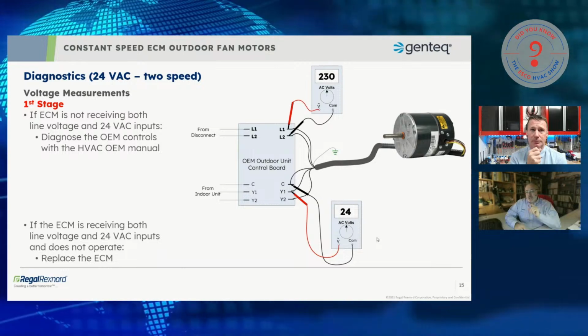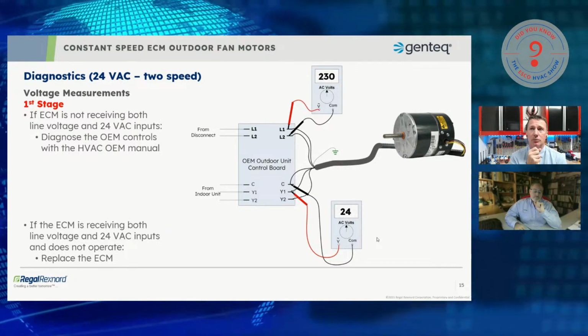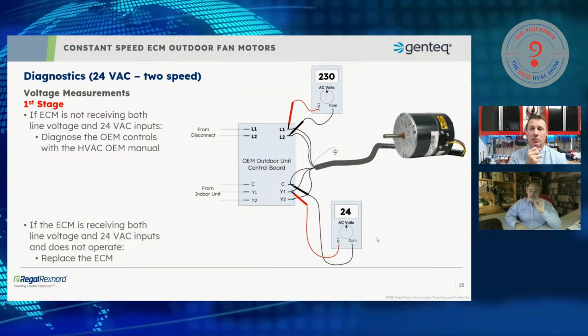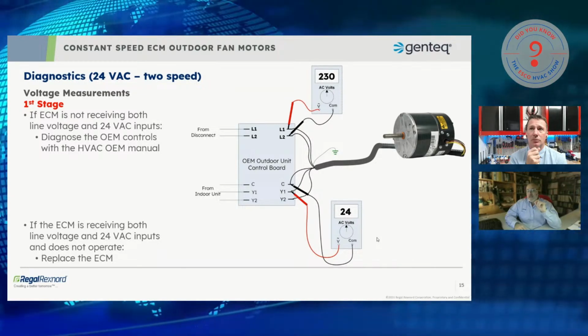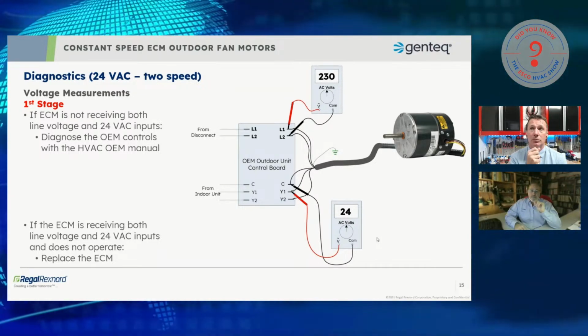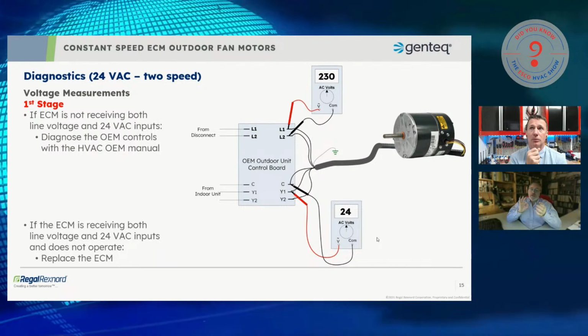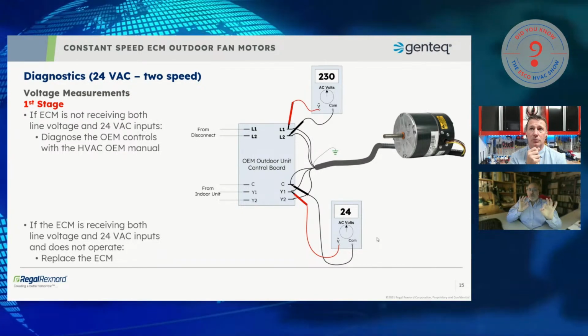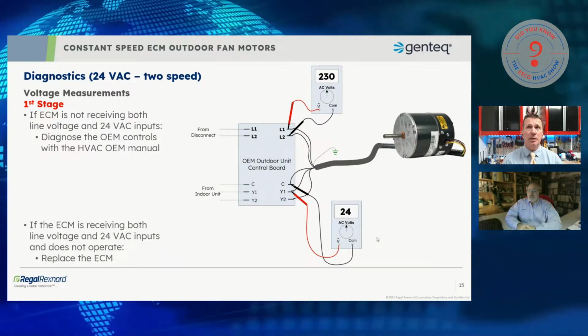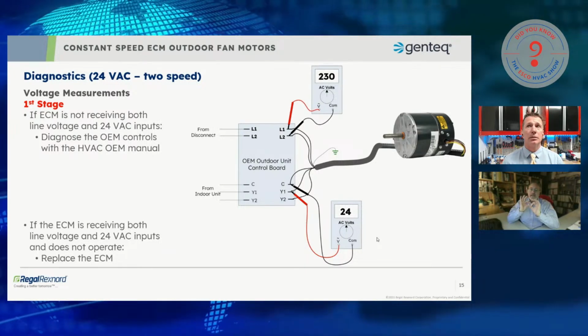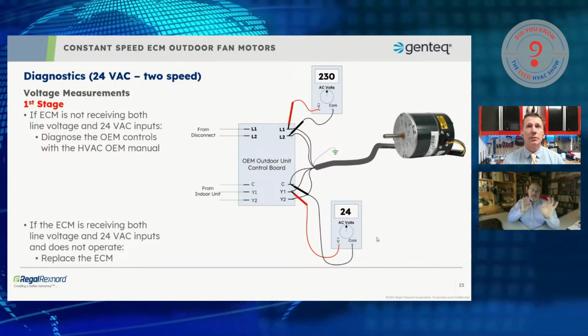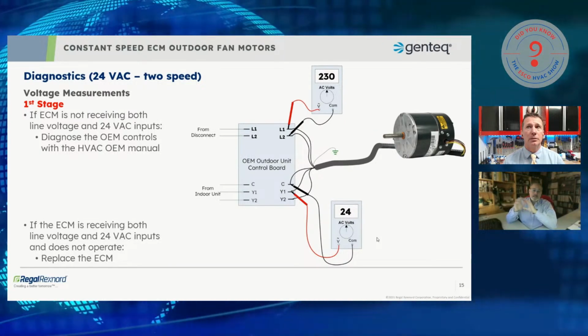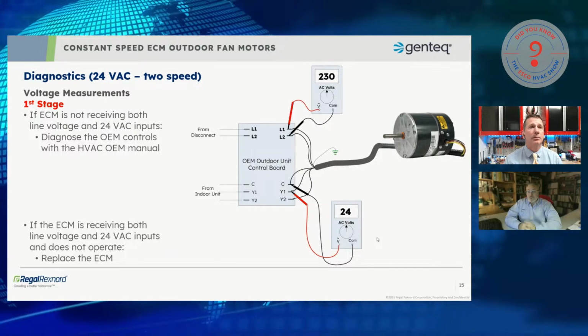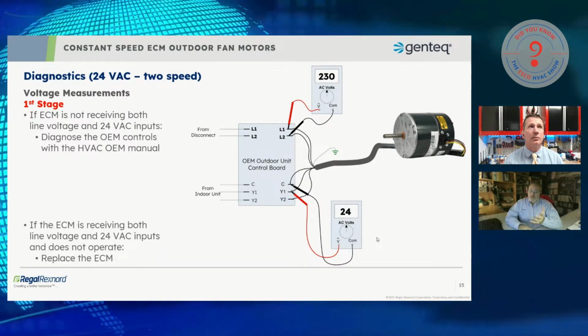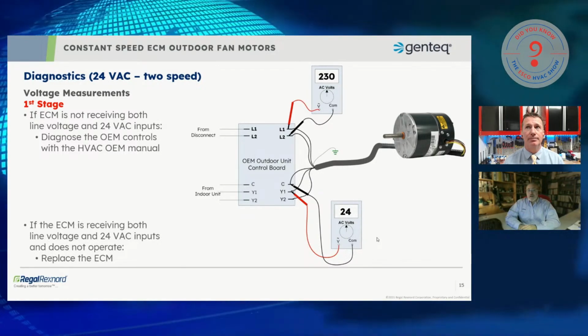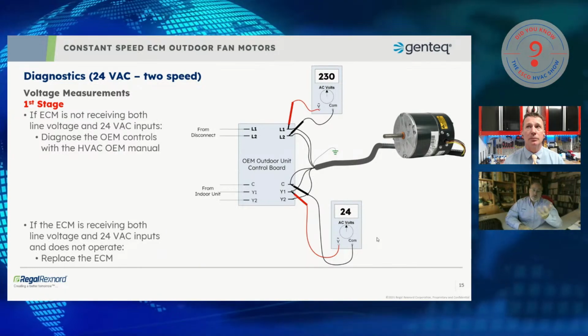Each one of these taps, when they're in 24-volt discrete mode, has something internally called an opto-isolator. And what that means is there's an optocoupler between where the 24 volts comes into the motor and where that signal actually makes it to the micro. It's sort of a safety circuit. So it is possible for one speed to have something blown that doesn't allow that signal to make it to the micro, and another speed to still work. Interesting. Again, in most cases, like you said, the motor either works on all speeds or it doesn't work on any speeds. But that's a question that I have been asked, so I thought it was worth bringing up here.